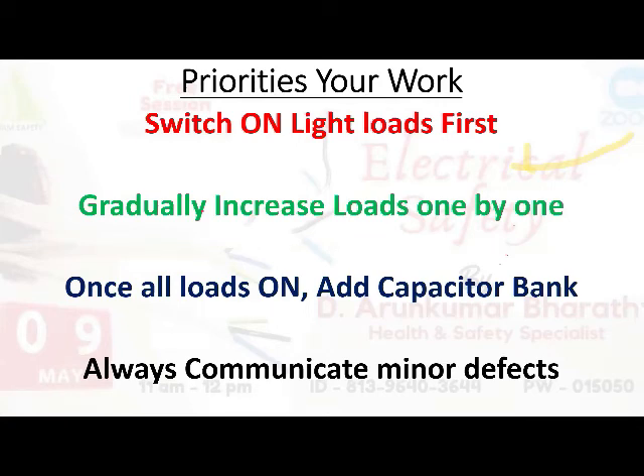It means something is wrong with the connection. What do you do at that point? Again, our basic philosophy: always check the track from supply to load, by measuring it or other means. Then gradually increase the load one by one. If you don't hear any noise or problem, you can switch on the next load, then the next. Once you switch on all the loads, finally you can add the capacitor bank. After switching on all the loads, then finally you can switch on the capacitors.